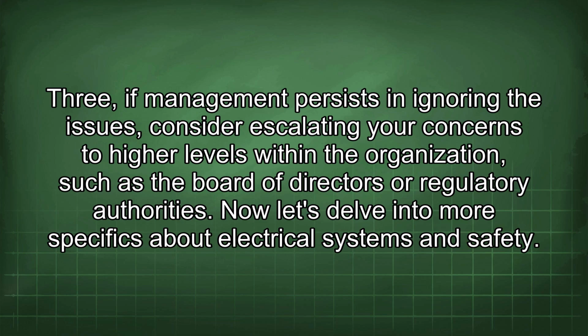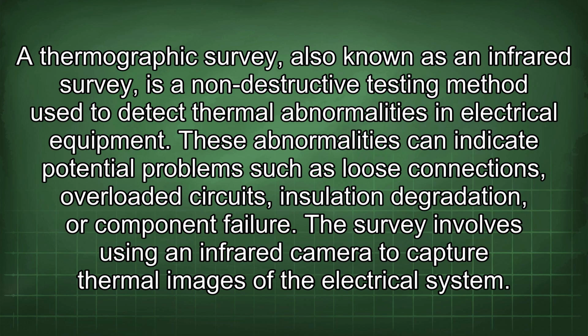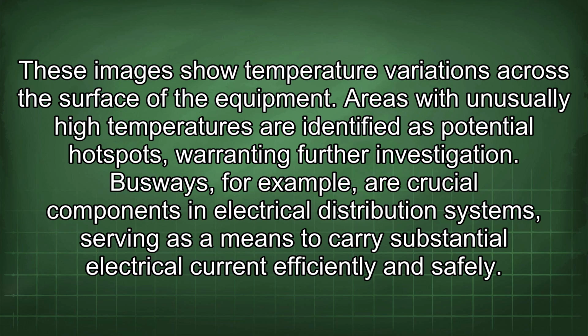Now let's delve into more specifics about electrical systems and safety. A thermographic survey, also known as an infrared survey, is a non-destructive testing method used to detect thermal abnormalities in electrical equipment. These abnormalities can indicate potential problems such as loose connections, overloaded circuits, insulation degradation, or component failure. The survey involves using an infrared camera to capture thermal images of the electrical system. These images show temperature variations across the surface of the equipment. Areas with unusually high temperatures are identified as potential hotspots, warranting further investigation.